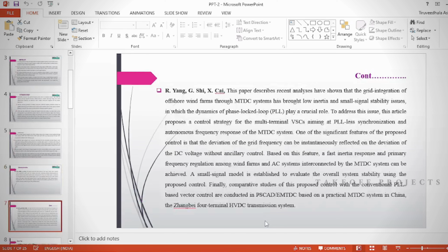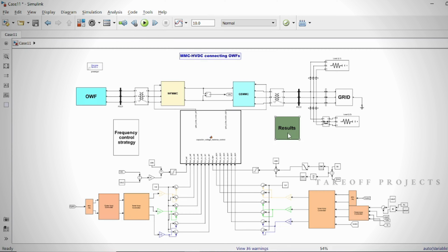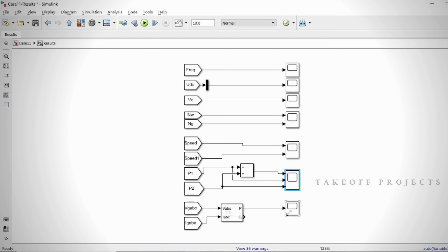Results. The structure of MMC HVDC connecting OWFs is, the sending end converter station on the WF side is defined as WFMMC, whose control mode is the AC voltage and frequency control, so as to provide voltage and frequency support for OWFs. The receiving end converter station on the grid side is defined as GSMMC, whose control mode is DC voltage and reactive power control, so as to maintain the power balance of MMC HVDC system.